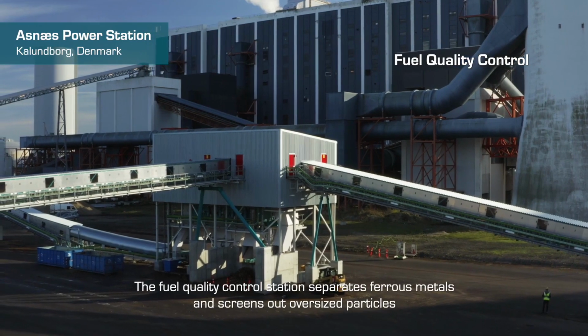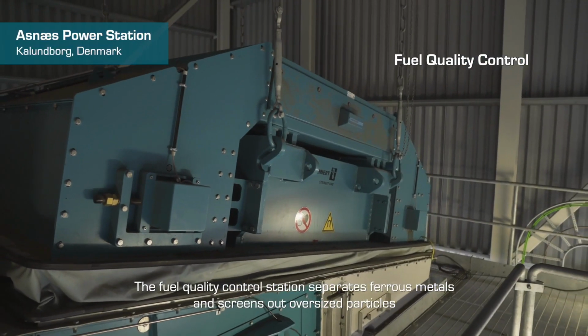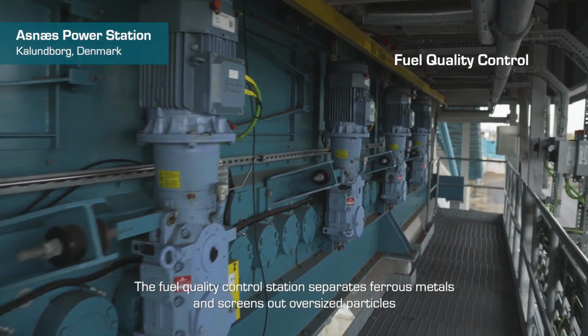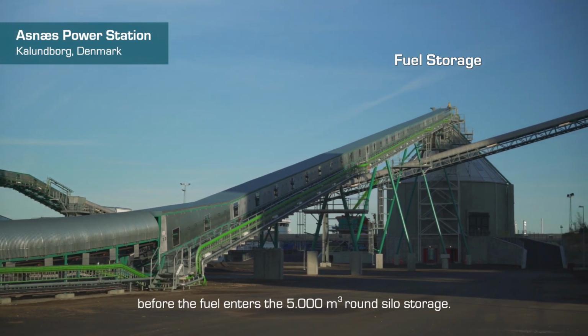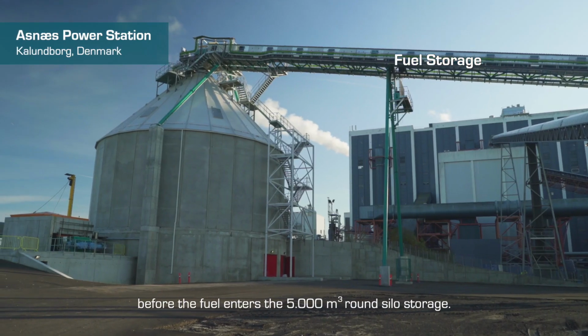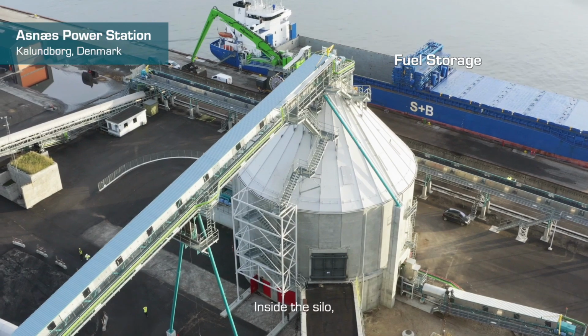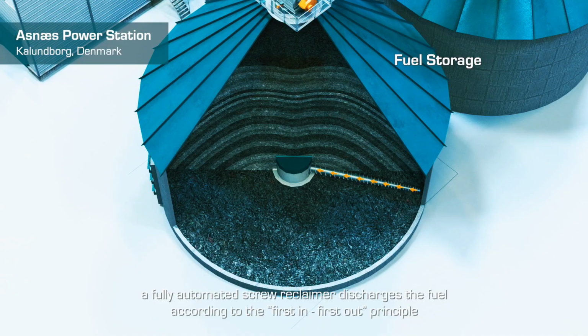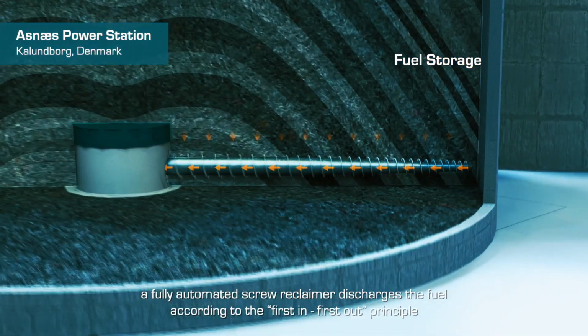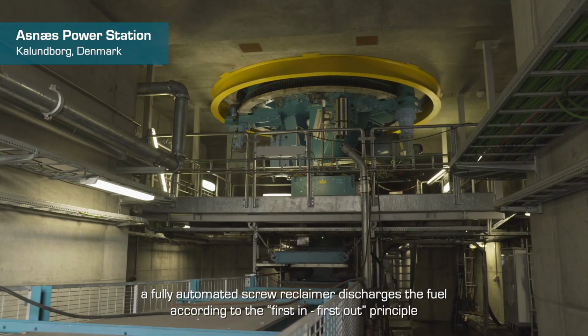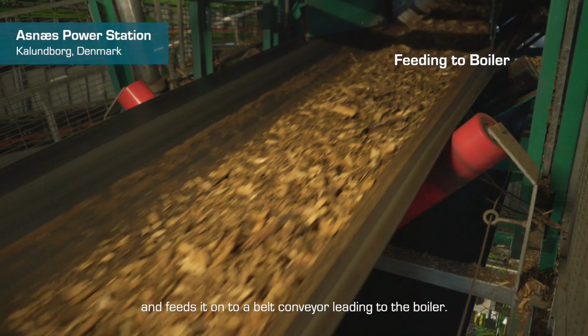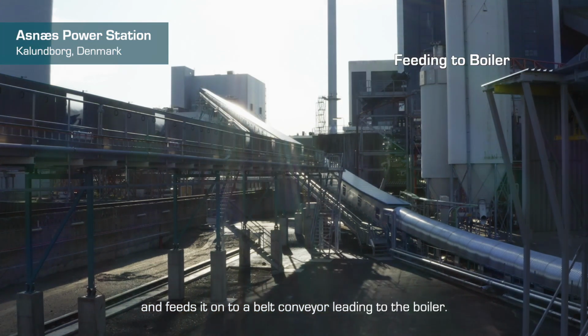The fuel quality control station separates ferrous metals and screens out oversized particles before the fuel enters the 5,000 cubic meter round silo storage. Inside the silo, a fully automated screw reclaimer discharges the fuel according to the first-in, first-out principle and feeds it onto a belt conveyor leading to the boiler.